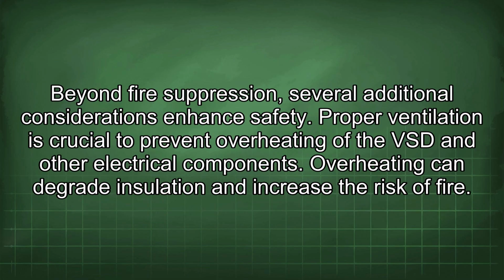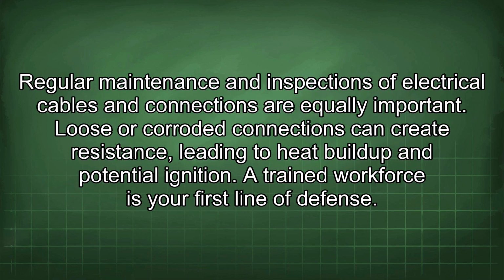Beyond fire suppression, several additional considerations enhance safety. Proper ventilation is crucial to prevent overheating of the VSD and other electrical components. Overheating can degrade insulation and increase the risk of fire. Regular maintenance and inspections of electrical cables and connections are equally important. Loose or corroded connections can create resistance, leading to heat buildup and potential ignition.